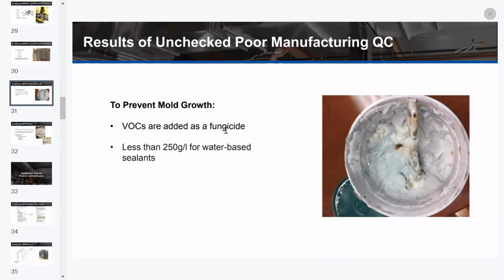So the results of unchecked poor manufacturing is just ensuring indoor air quality, right? Being aware of what is in the product that is intended for the use. To prevent mold growth, you need to look for sealants and mastics that do have some VOCs. And those VOCs are going to be added as a fungicide, which is actually also required by the UL 181 requirements when you're talking about a UL listed product.